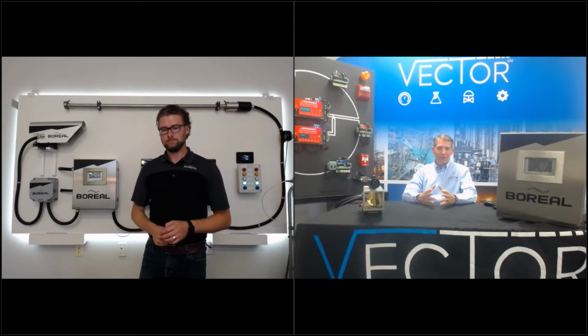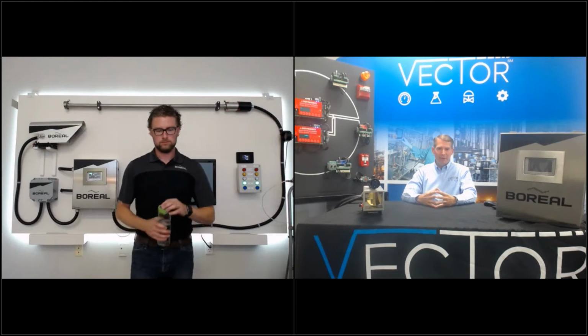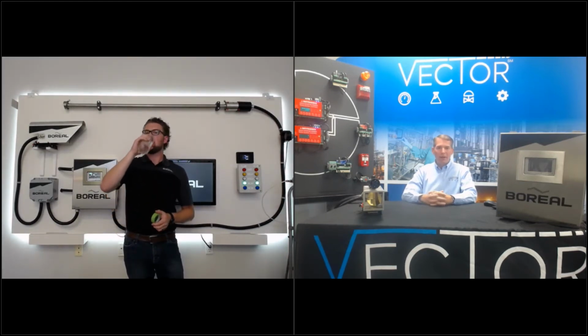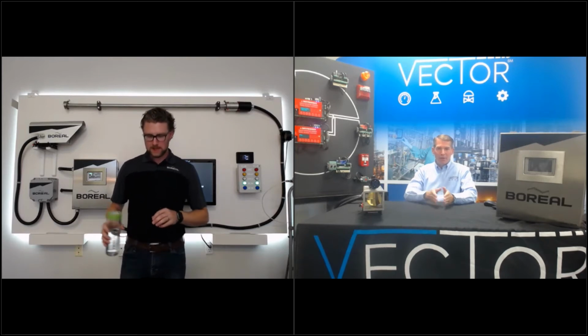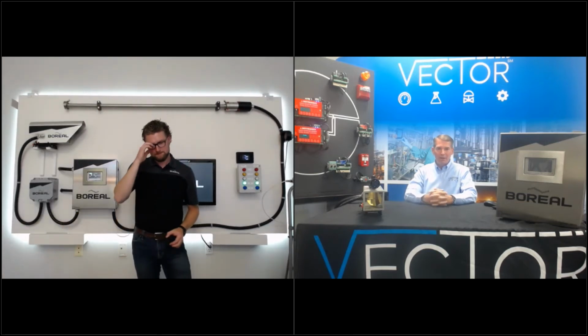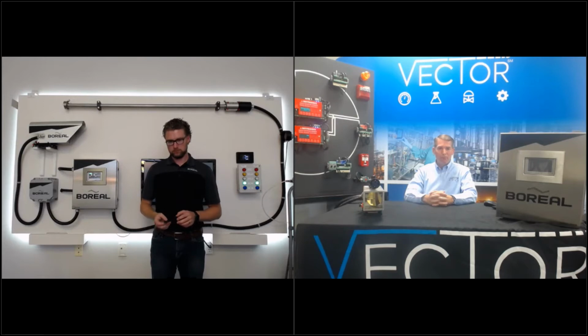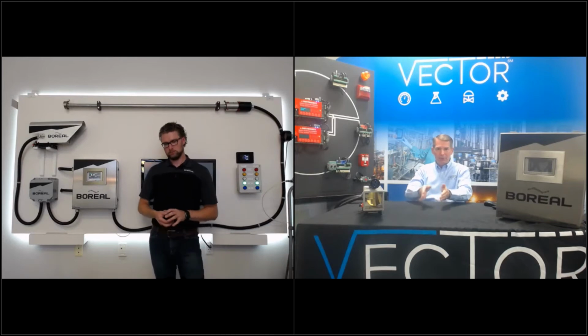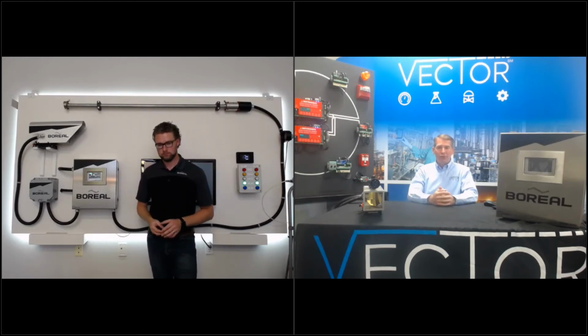The one thing that you did touch on there: your setup behind you is tuned to methane, and then you referenced that you have a facility with these installed that's looking for H2S. I want to make sure that everybody understands that the laser gas detector we're talking about today has the capability to do both combustible and toxic gas detection. Kyle did mention that they're tuned for a specific gas. But what the gas finder allows you to do with multiple heads is have a tuned H2S, a tuned methane, maybe a tuned ammonia, HF. So you have the ability to actively look for more than one gas based on the number of heads you have available for each gas finder. Very cool technology that allows not only detection for hydrocarbons or combustibles, but toxics as well.